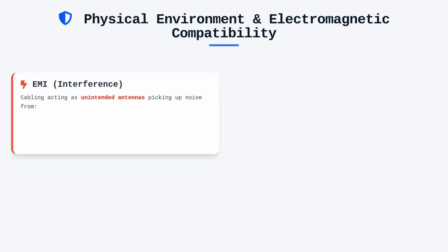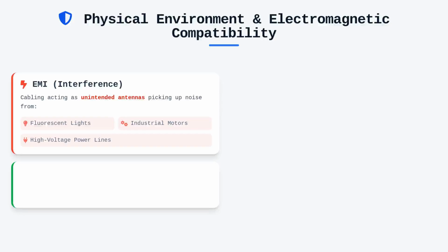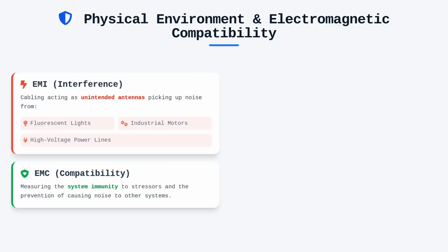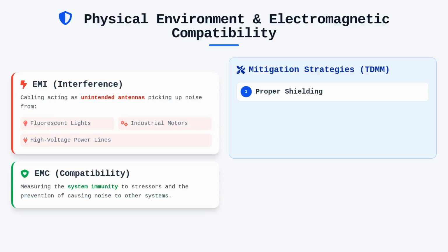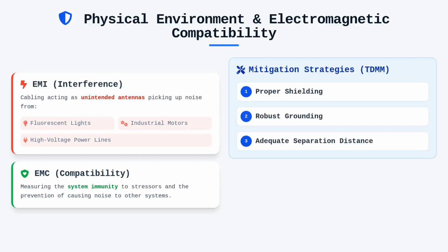However, our duty extends well beyond the transmission of bits. We must account for the physical environment and electromagnetic compatibility. Electromagnetic interference, or EMI, can turn our cabling into an antenna that picks up noise from fluorescent lighting, motors, or power lines, while electromagnetic compatibility, or EMC, measures our system's immunity to these external stressors and its propensity to cause interference elsewhere. Effective mitigation strategies involve proper shielding, grounding, and maintaining adequate separation distances from potential noise sources, all of which are documented requirements in the TDMM.